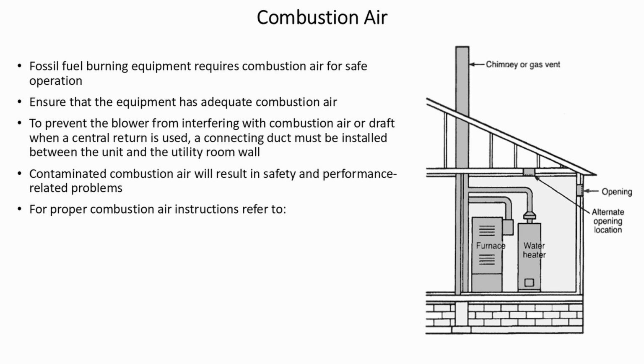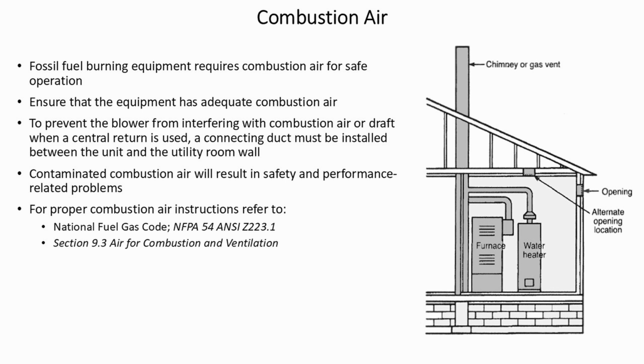For proper combustion air instructions, refer to National Fuel Gas Code NFPA 54 ANSI Z223.1, Section 9.3 Air for Combustion and Ventilation, 9.3.2.1 Standard Method. The minimum required volume shall be 50 cubic feet per 1,000 BTU per hour.